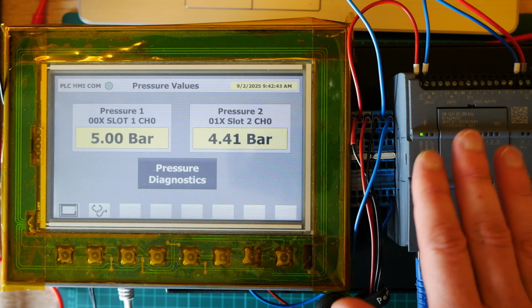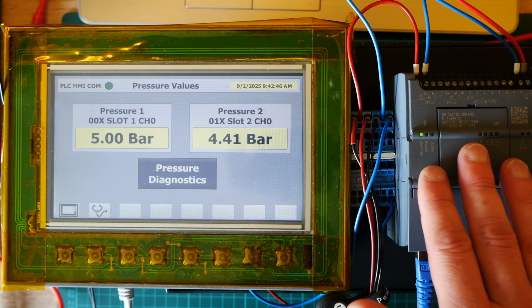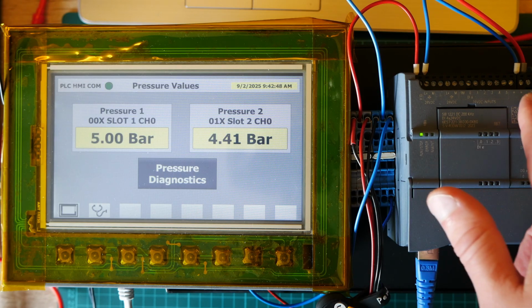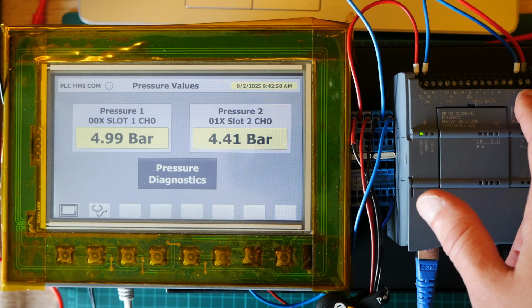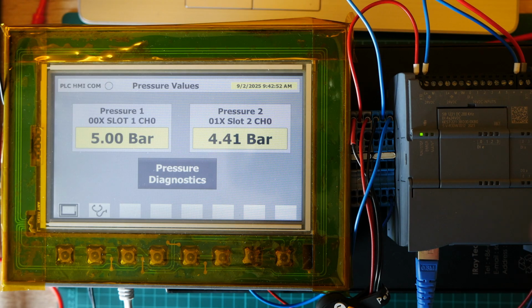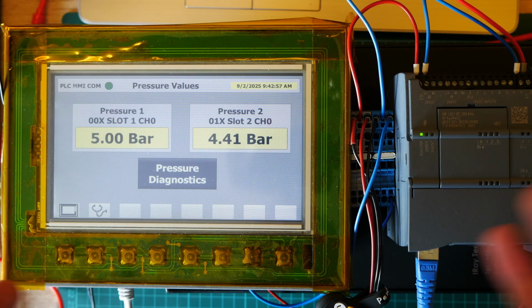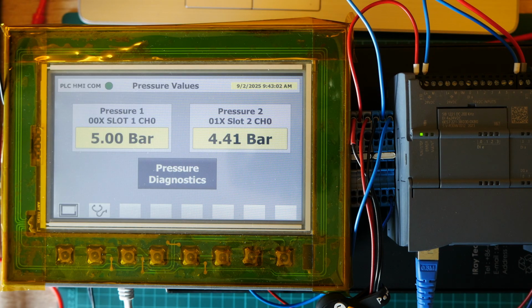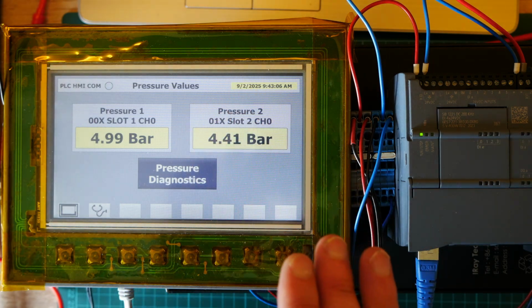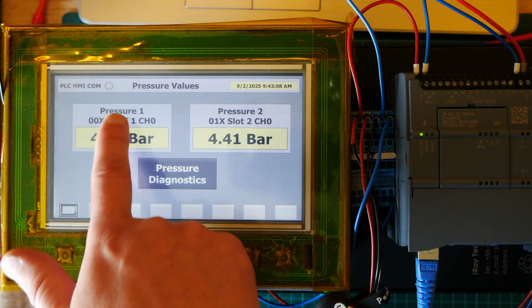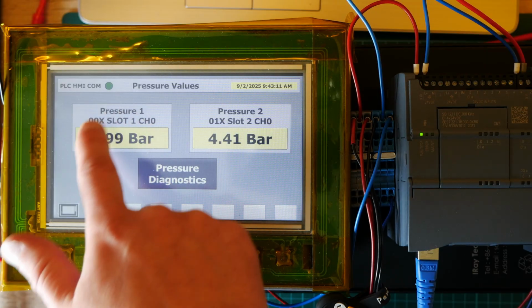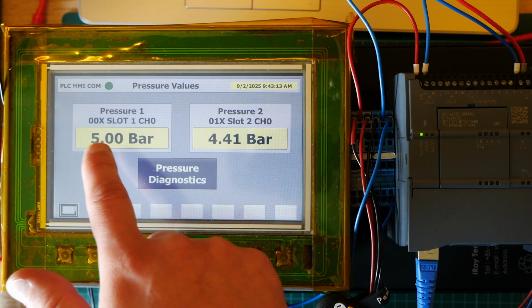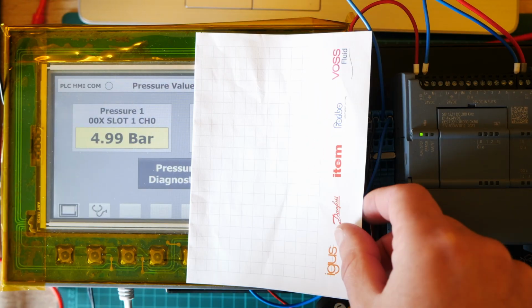Because it can be an issue in the program itself. It could be an issue with the analog input. It could be a wiring issue, or it could be a sensor issue. So where to start and how to solve it? First thing that I would suggest, right now we are only talking about this reading. This reading is from 0 to 10 volts. Yes, so let's focus on this one.